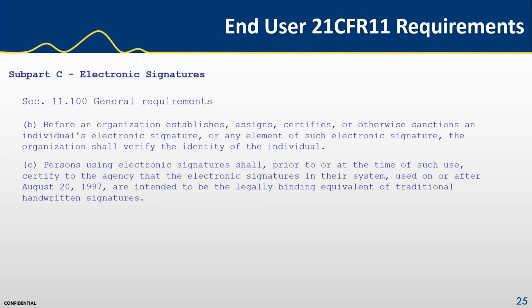There are more. And I wanted to illustrate that in order for any company to be fully compliant to 21 CFR Part 11, they must adhere to the full requirements themselves. That's why I never say that we supply a fully 21 CFR Part 11 compliant instrument or system, because there are these obligations of the end user to fulfill. And sometimes these end users do not understand that, but it's really important that you do.